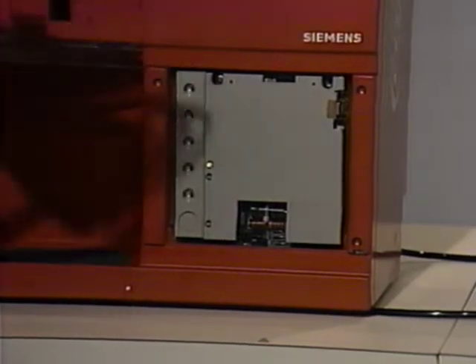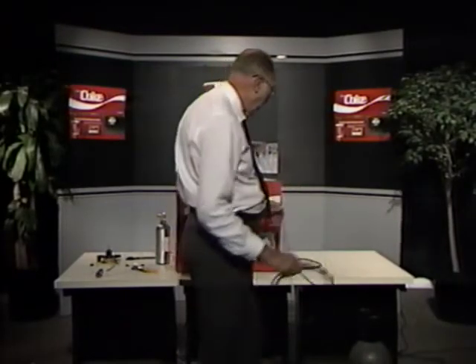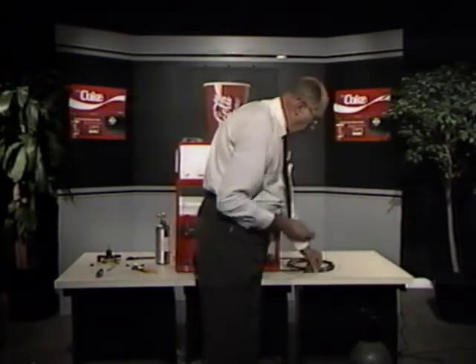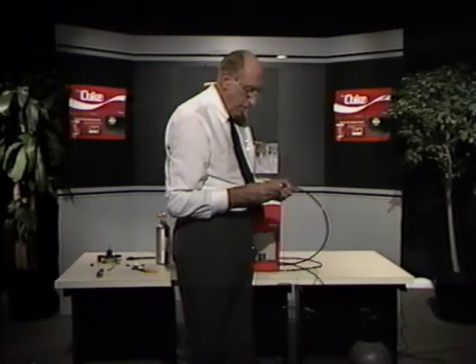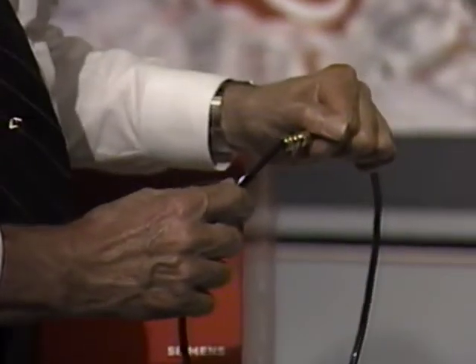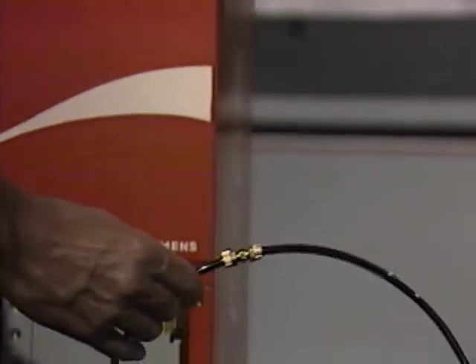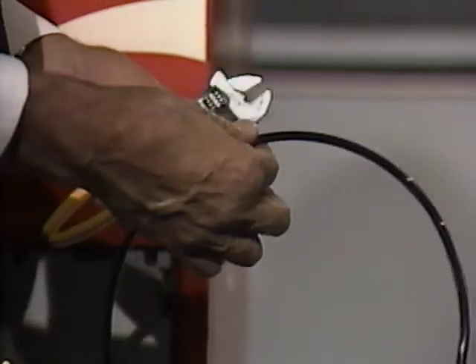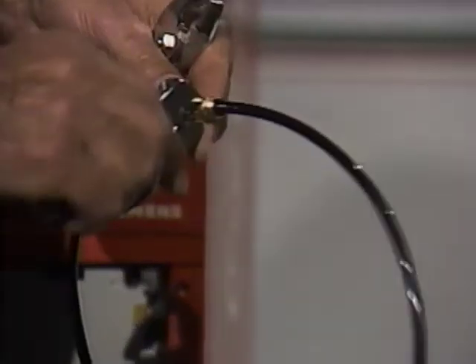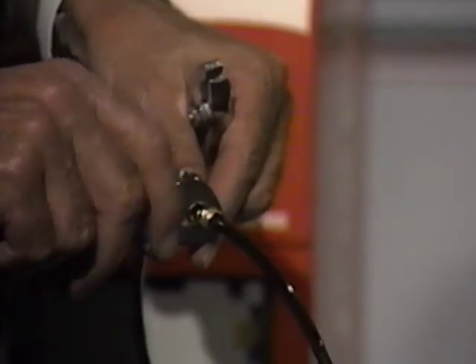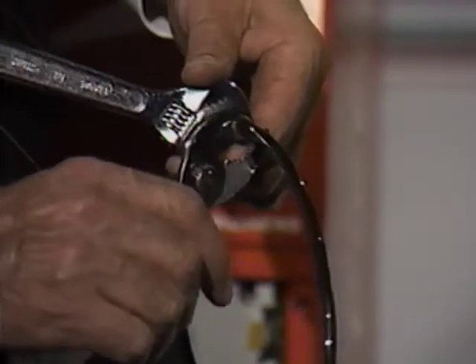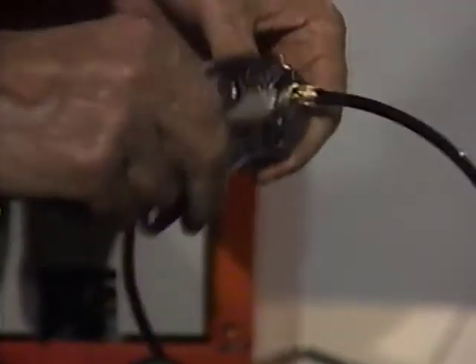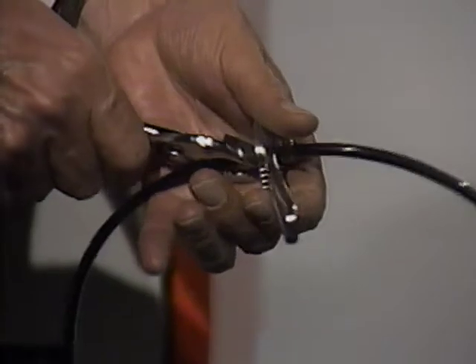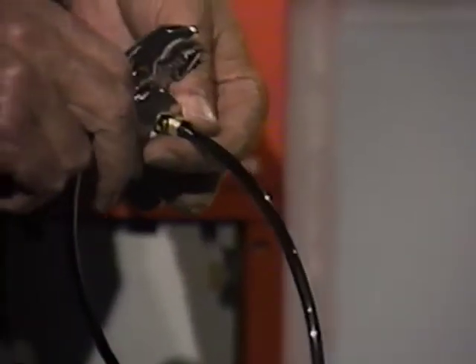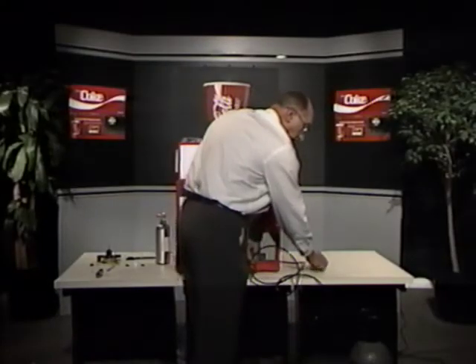The next step will be to couple our extension hose to the tubing that's come from the bracket. We're going to use the coupling. Simply push the tubing into the coupling. Then we tighten it finger tight on both sides. And tighten it up an extra quarter to a half turn. Don't over tighten the coupling because the plastic bushings in there will tend to break if they are over tightened.